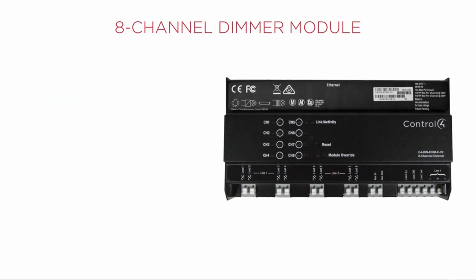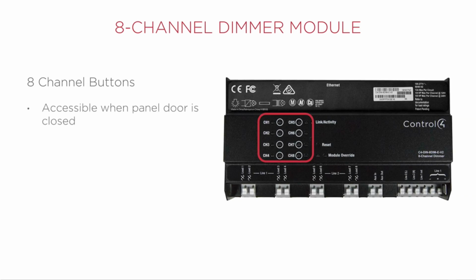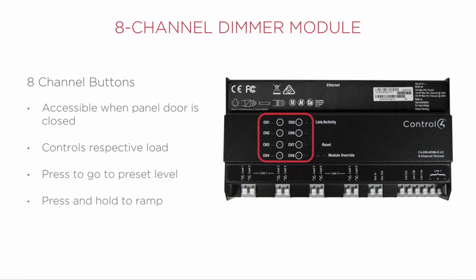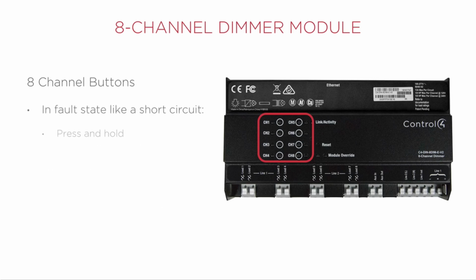The Control4 dimmer module has 8 channel buttons, which are accessible when the panel door is closed. Each button controls the respective load. Pressing the button goes to the preset level. Pressing and holding the button will ramp the load up or down. In a fault state, press and hold the button, which will reset any fault state.